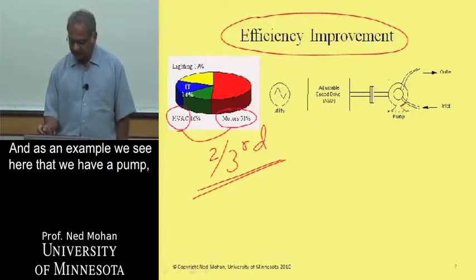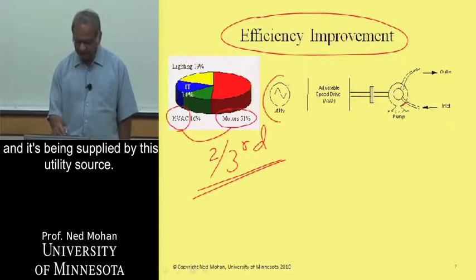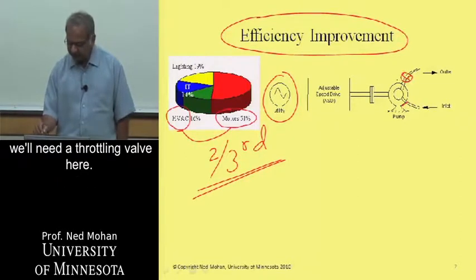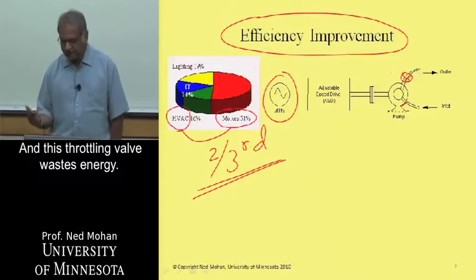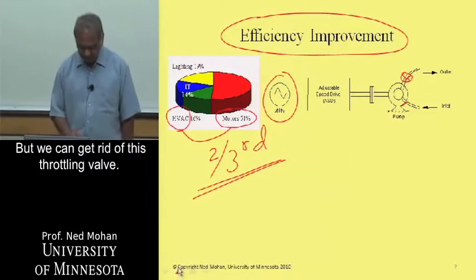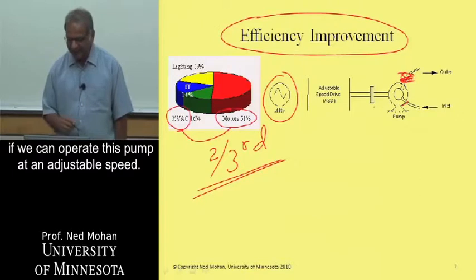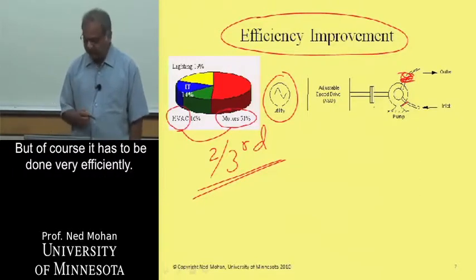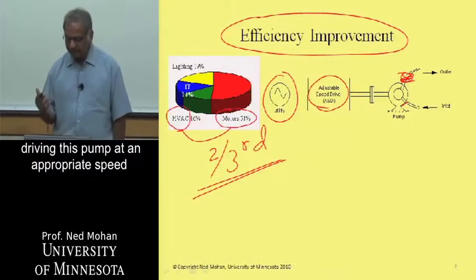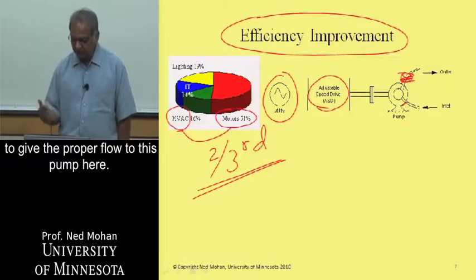As an example, we have a pump being supplied by a utility source. If we want to control the flow rate through this pump, we need a throttling valve, and this throttling valve wastes energy — that would be the case if this pump was being driven at a constant speed. But we can get rid of this throttling valve if we can operate this pump at an adjustable speed, done very efficiently, to give the proper flow through this pump.